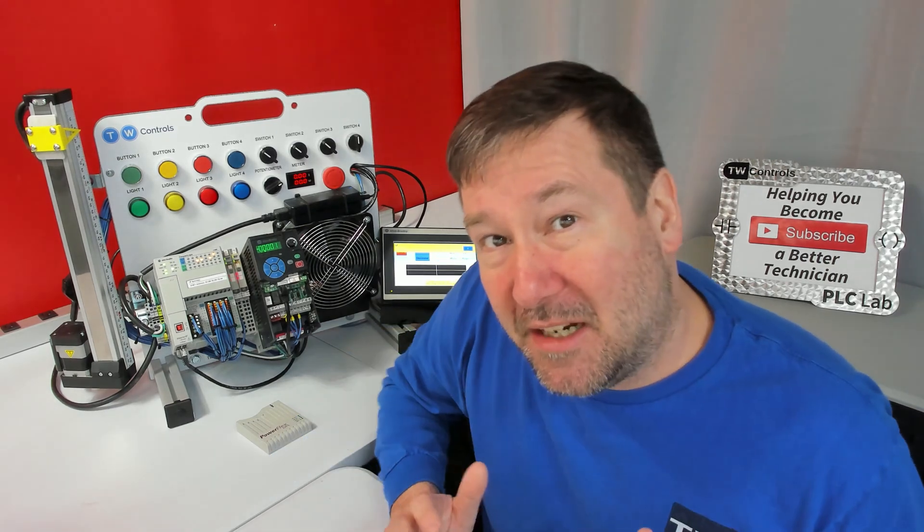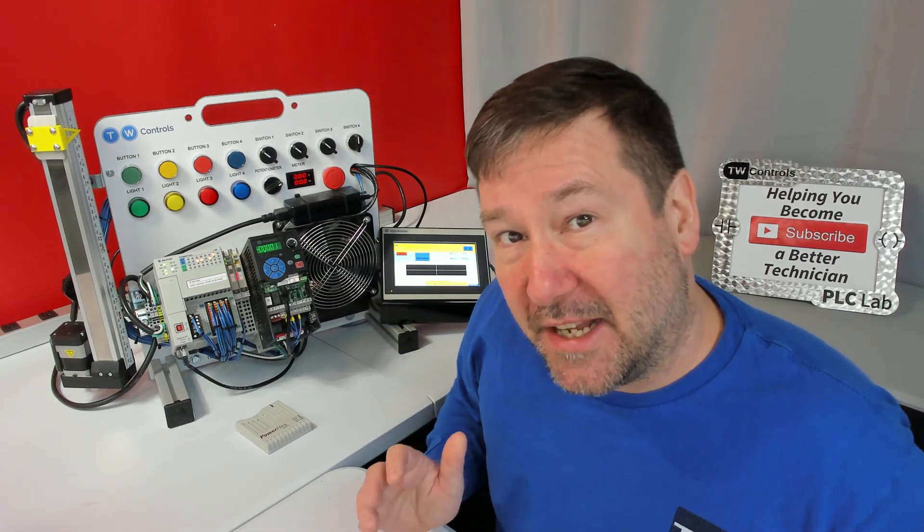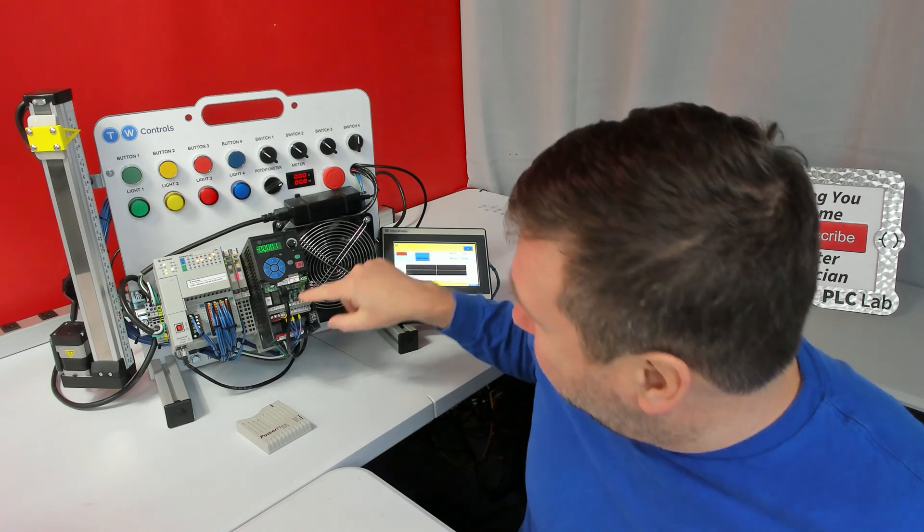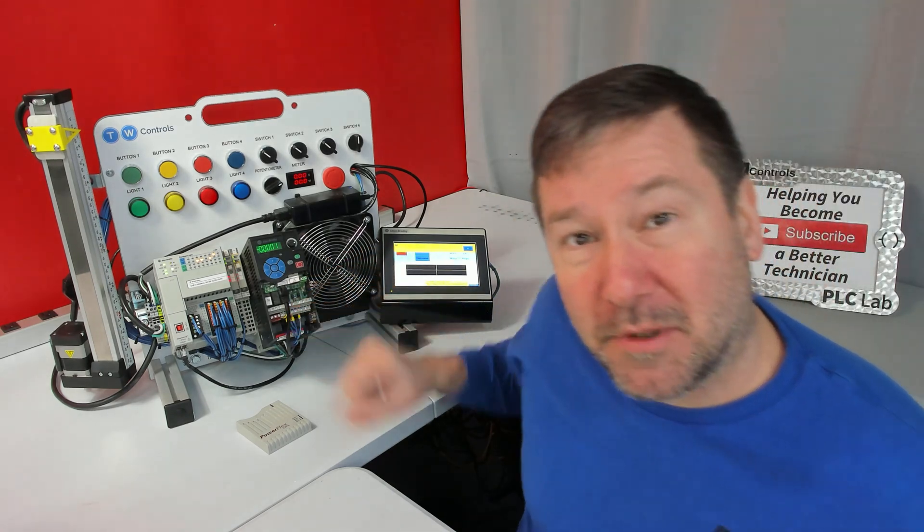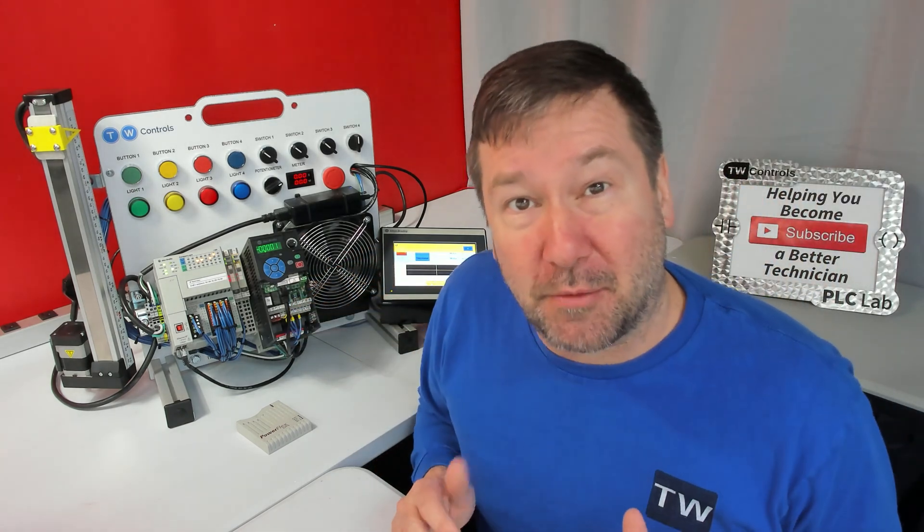When troubleshooting the I.O. states of a PowerFlex 525, we need to know the I.O. states on the digital input terminals, and specifically terminals 2 and 3.